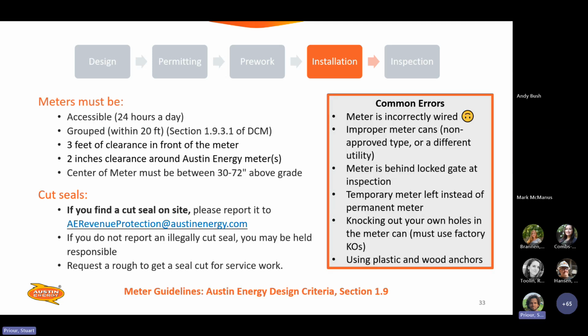So a little more about meters. They've got to be accessible 24 hours a day to our metering team. They need to be grouped within 20 feet. They need to have 3 feet of clearance in front of them. They need to have 2 inches of clearance around the meter can itself, so on all sides, you need 2 inches of clearance. Pro tip, an offset nipple is not quite 2 inches, so you'll need some additional hardware to get to that 2-inch clearance. And the center of the can has got to be 30 inches to 72 inches from final grade too.